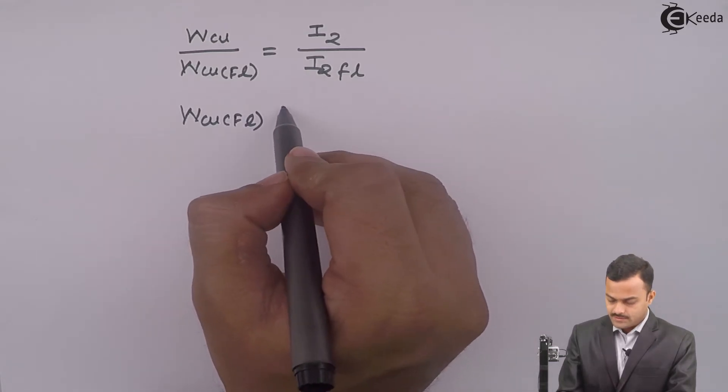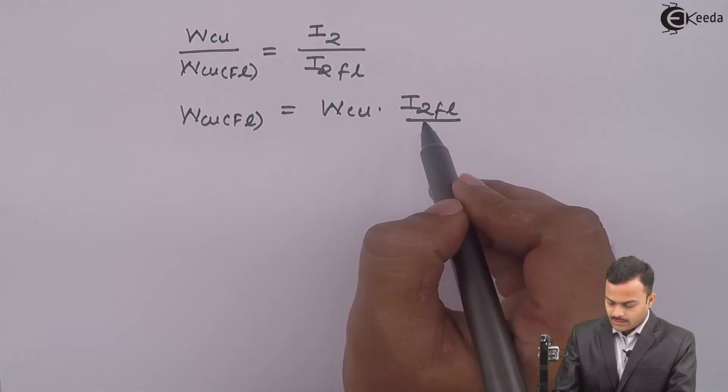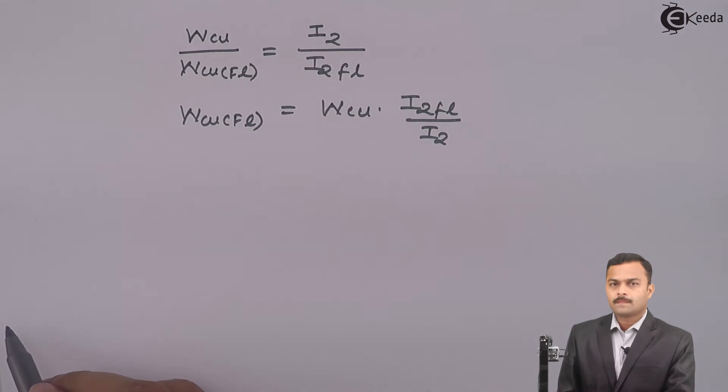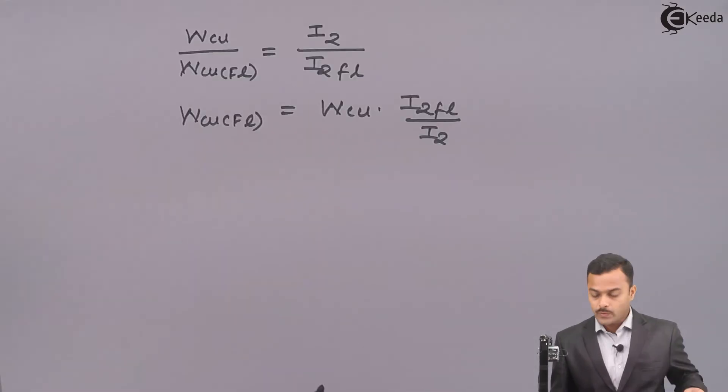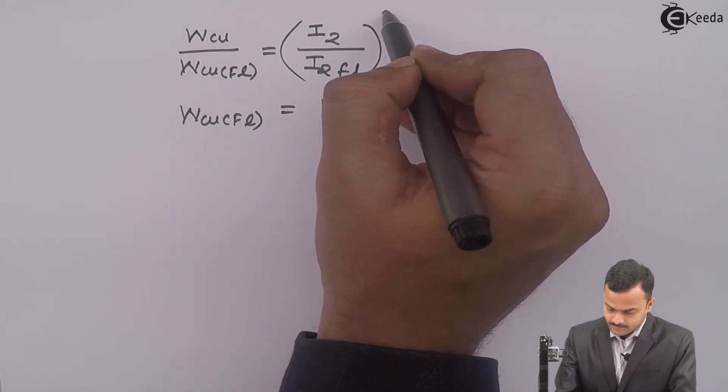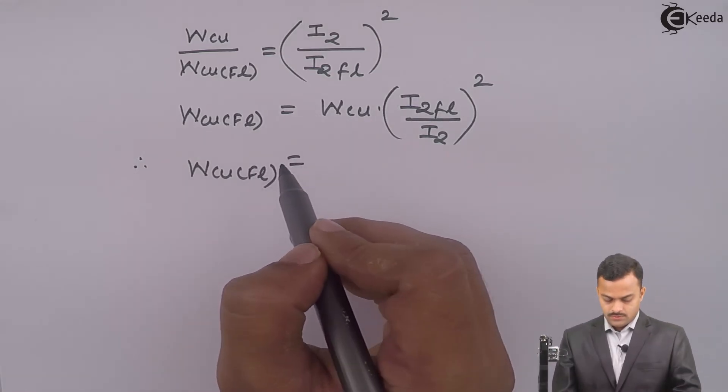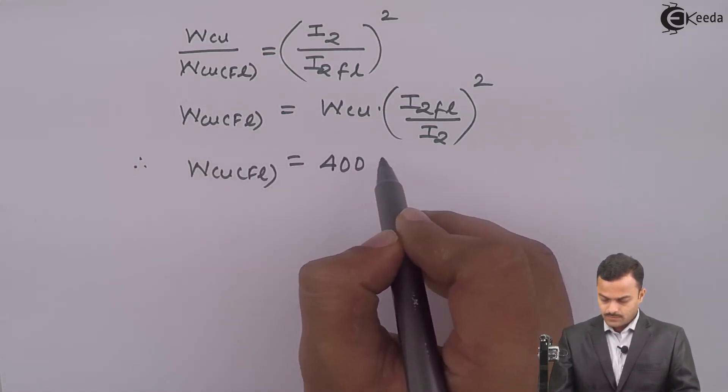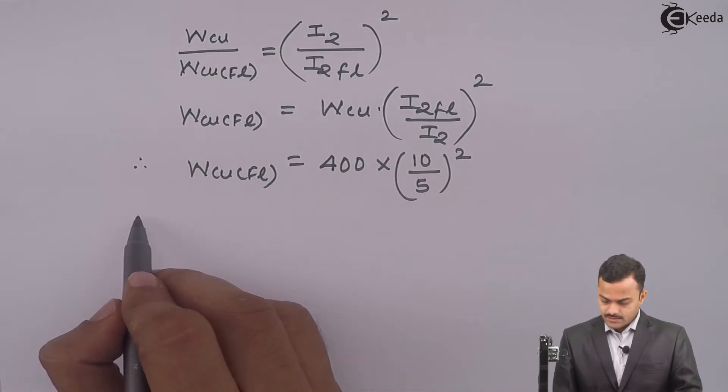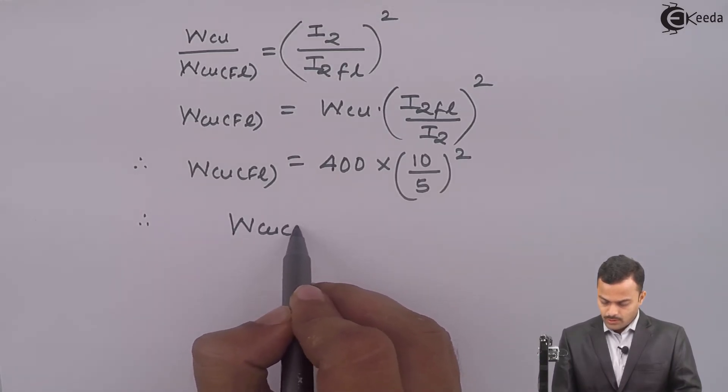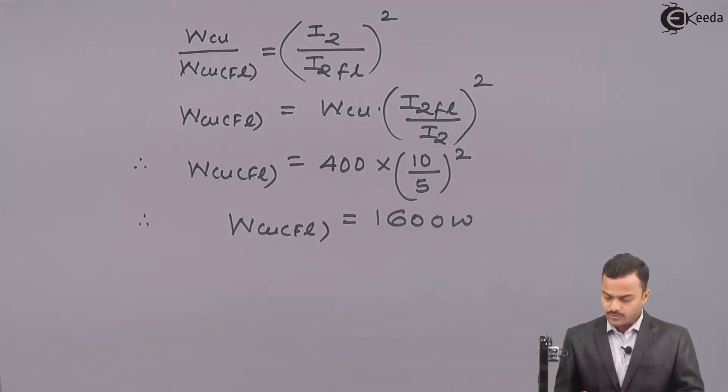So WCUFL is WCU multiplied by I2FL divided by I2. If you see here, it is directly proportional to square of current. So actually it is square. So WCUFL equals 400 times (10/5)². So if you solve this, you will get full load copper loss WCUFL equal to 1,600 Watt. A very important finding.